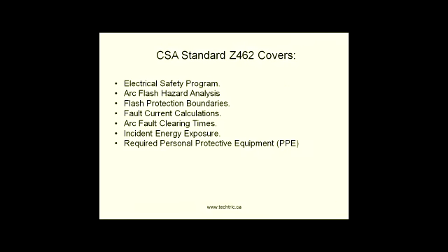Now, some CSA content I'm going to cite here. CSA standard Z462 covers the electrical safety program, arc flash hazard analysis, arc flash protection boundaries, fault current calculations, arc clearing times, incident energy exposure, and required personal protective equipment that has to do with working on electricity, okay?